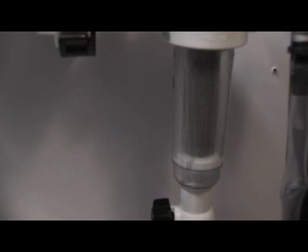If you don't want anything visible coming out of this hose, then you want a 10 micron filter to take that out, because a 10 micron filter is going to remove all visible solids, okay? And we would have to find a canister that would fit a 10 micron filter. It wouldn't be this canister, it would be another one, okay?